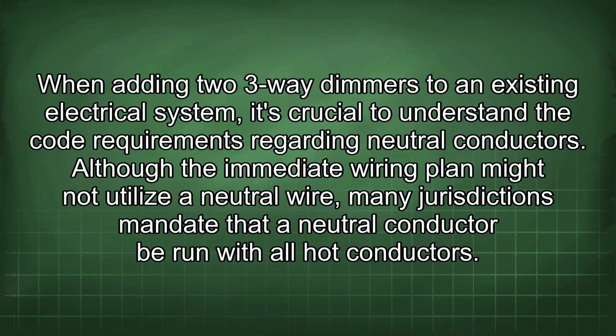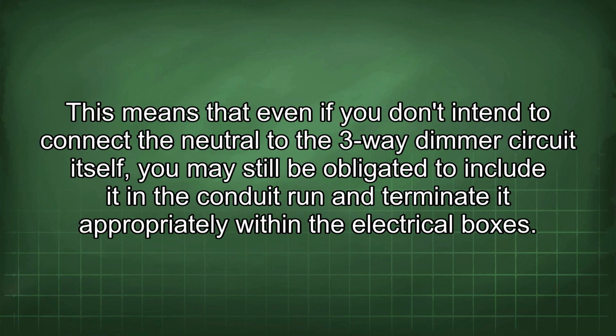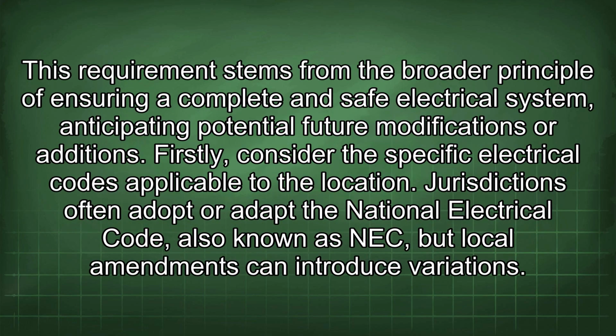When adding two three-way dimmers to an existing electrical system, it's crucial to understand the code requirements regarding neutral conductors. Although the immediate wiring plan might not utilize a neutral wire, many jurisdictions mandate that a neutral conductor be run with all hot conductors. This means that even if you don't intend to connect the neutral to the three-way dimmer circuit itself, you may still be obligated to include it in the conduit run and terminate it appropriately within the electrical boxes.